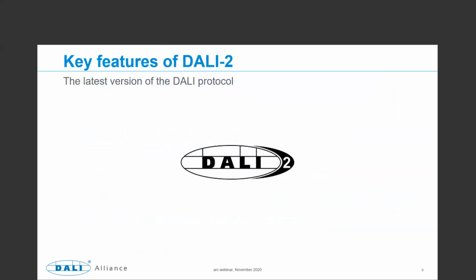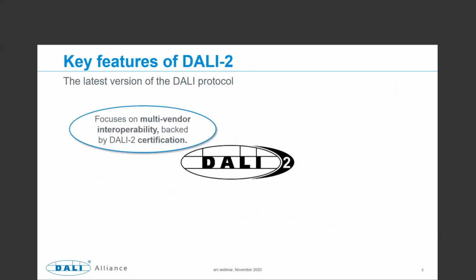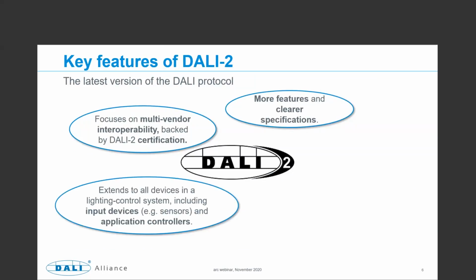So some key features of DALI-2. It's the latest version of the DALI protocol, and it focuses on multi-vendor interoperability backed by our DALI-2 certification. DALI-2 has more features and clearer specifications compared to the original DALI version 1. It extends to all devices in a lighting control system, including the input devices such as the sensors and application controllers, the devices that take control and make decisions.